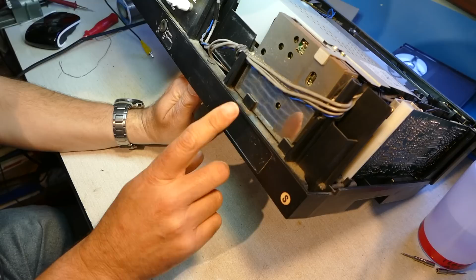If you're finding you're getting a lot of dropouts which don't seem to be handled properly - white streaks rather than what should happen, which is the line above the dropout being repeated, so you lose vertical resolution - if you think it's not handling dropouts particularly well, a small adjustment to the dropout compensator can help. I've found that the VTCM series machines, such as the VTC5000, are particularly prone to that.